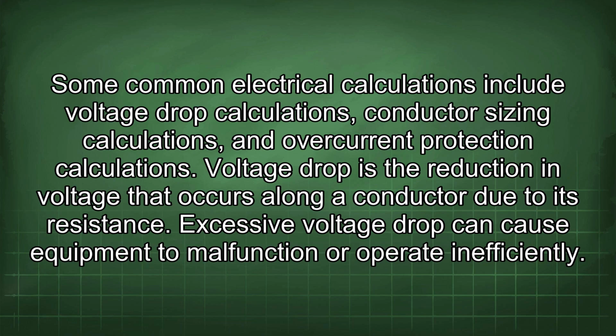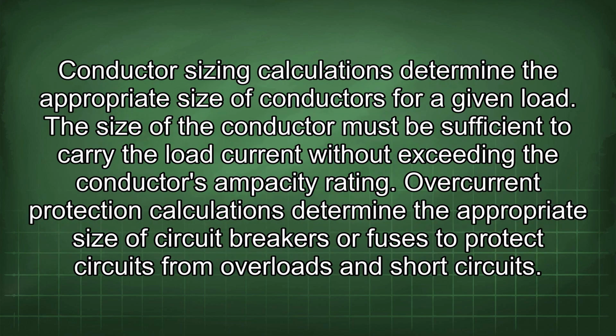Voltage drop is the reduction in voltage that occurs along a conductor due to its resistance. Excessive voltage drop can cause equipment to malfunction or operate inefficiently. Conductor sizing calculations determine the appropriate size of conductors for a given load. The size of the conductor must be sufficient to carry the load current without exceeding the conductor's ampacity rating.